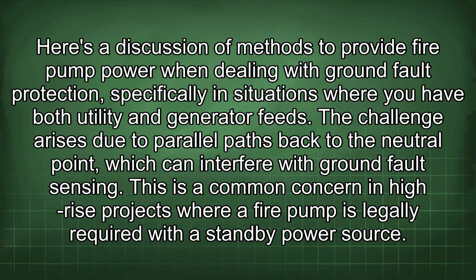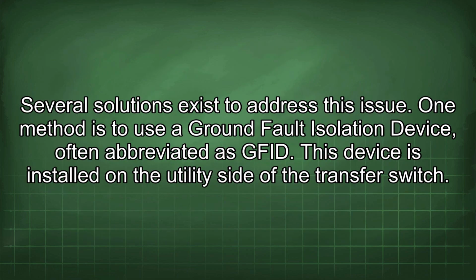Here's a discussion of methods to provide fire pump power when dealing with ground fault protection, specifically in situations where you have both utility and generator feeds. The challenge arises due to parallel paths back to the neutral point, which can interfere with ground fault sensing. This is a common concern in high-rise projects where a fire pump is legally required with a standby power source. Several solutions exist to address this issue.